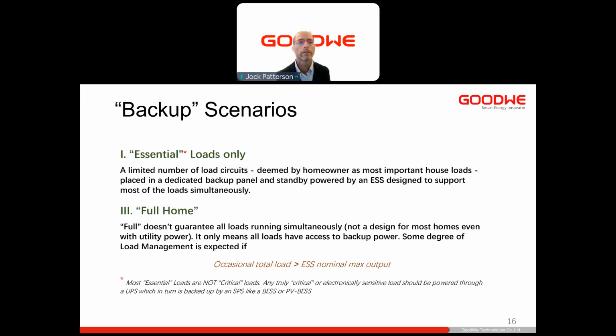A word on the word essential. These are loads that you would like to have run, but they're not considered critical loads by any authority. Critical load is defined differently by the NEC. And if you truly have a critical load, like an oxygen generating machine, those should be connected to a UPS, which in turn can receive further backup power by the SPS, that is the ESS that you provide your customer.